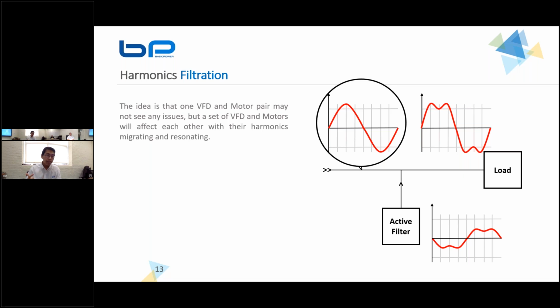And the idea of this setup is, again, to prevent the harmonic distortion from migrating between loads and upstream to affect other equipment like generators, or in your distribution, a transformer that might heat up, and the lead times for that equipment might be super long. So we want to prevent any downtime and maintenance on that equipment by alleviating it from stress.